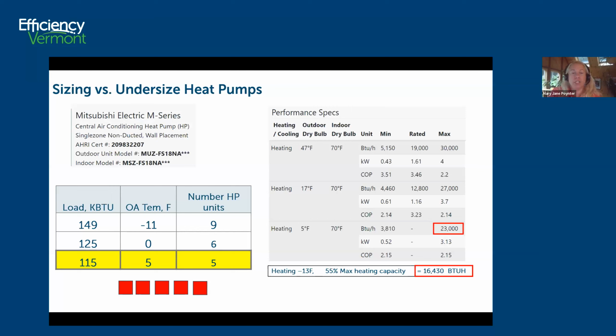And if they have a functioning backup heating system, and if it's hot water, then there's an option to go with the air to water unit at a later date. We also need to think about the fact that these mini splits have a life of about 15 years. And when that 15-year mark comes along, we're going to be switched over to a new type of refrigerant in all of the heat pumps. So unfortunately, that means that all the refrigerant lines have to be swapped out, as well as the indoor and outdoor units. And at that point, you could make some more changes to pick up the load of the entire building. And by then, your backup fossil fuel system will probably have been at the end of its life.